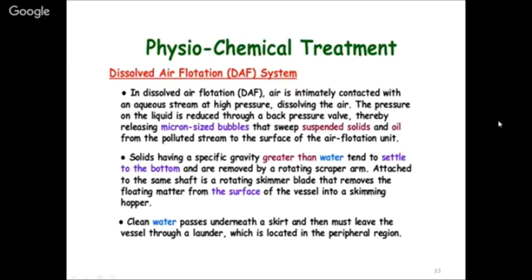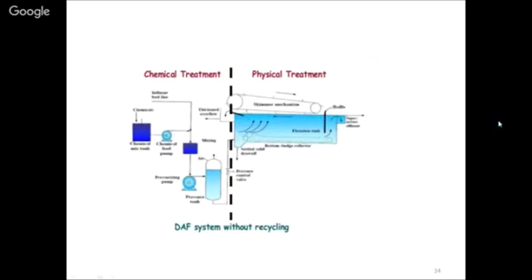Dissolved Air Flotation (DAF) is a physical-chemical treatment combining both physical and chemical processes. An aqueous stream is saturated with air at high pressure; when the pressure is reduced through a back-pressure valve, air bubbles form and float fine particles to the surface. Solids with specific gravity greater than water settle at the bottom and are removed by a rotating scraper. DAF is used to accelerate removal of fine particles by forcing air to attach to them, which is the dissolved air flotation cell principle.